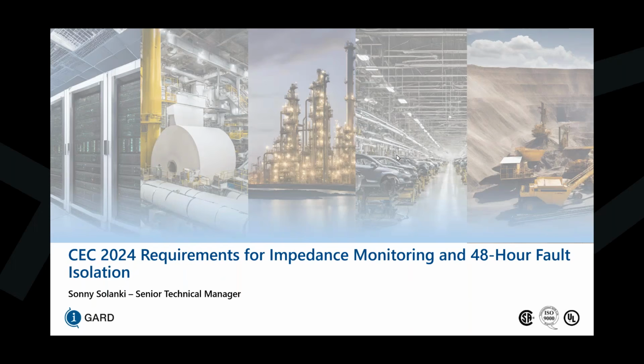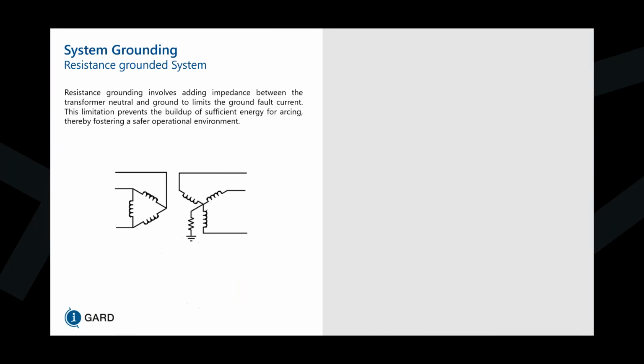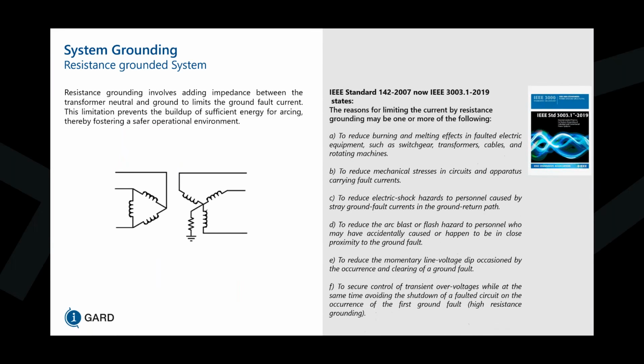Thank you, Devansh. Today's topic is going to be on the Canadian Electrical Code 2024 requirements for impedance monitoring and 48-hour fault isolation. So we're just going to go through resistance grounded systems. Resistance grounding involves adding impedance between the transformer neutral and ground to limit the ground fault current. And this limitation prevents the buildup of sufficient energy for arcing, thereby fostering a safer operational environment. So when we have a ground fault on one of the phases to ground, this resistor is essentially in series with the ground return path, and that's how we can limit the fault current to a specific value.